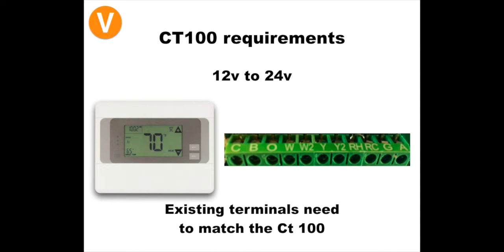First off, some of the requirements for our CT100 thermostats. First, the voltage range is 12 to 24 volts. So basically, if the wires are small enough to fit into the terminals on our terminal strip right here on the CT100, usually your voltage is going to be okay. If you do want to check it, you can always pull out your multimeter and check the voltage.